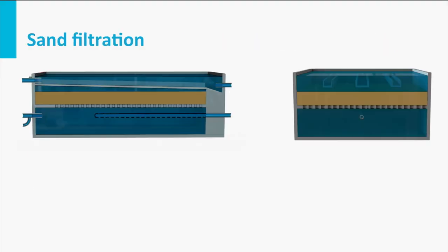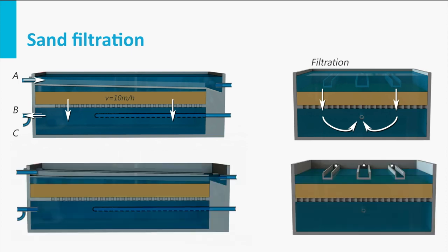Aeration is followed by sand filtration, where the oxidized ferric iron hydrolyzes to iron hydroxide flocs, which are removed by filtration in the sand bed. Manganese undergoes a partial chemical and biological transformation, while ammonium is biologically degraded by bacteria to nitrate. The growth of these bacteria in combination with the iron and manganese flocs result in an increase of the filter resistance, and backwashing is needed to prevent clogging.